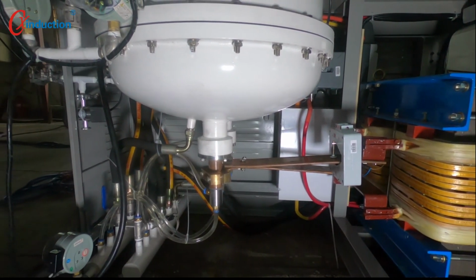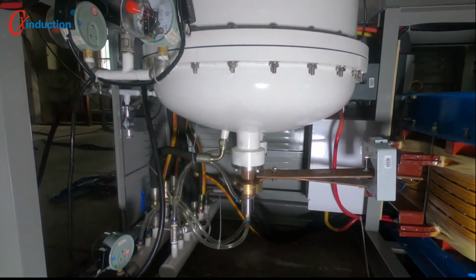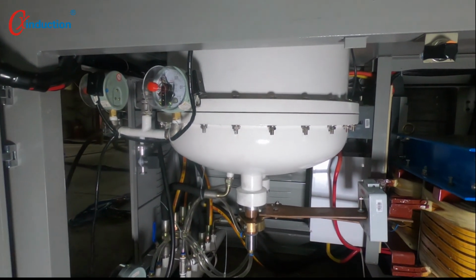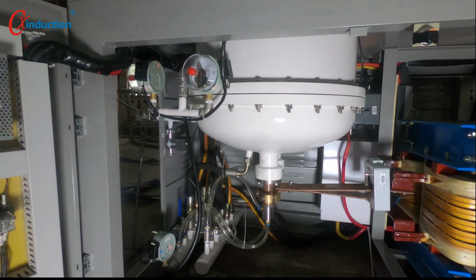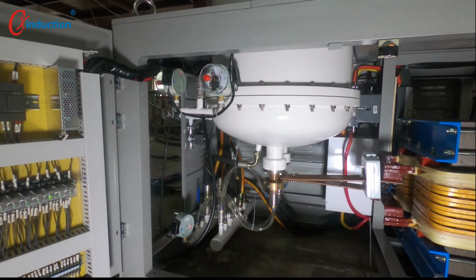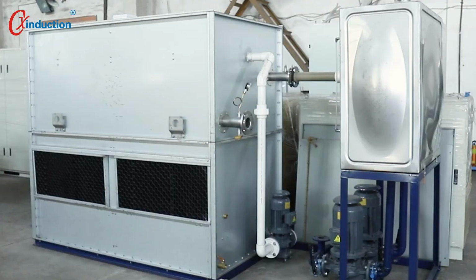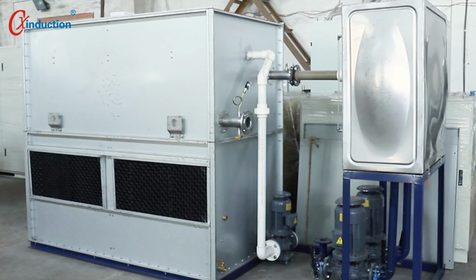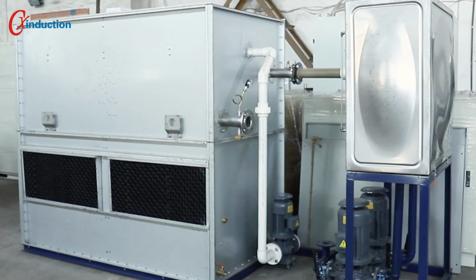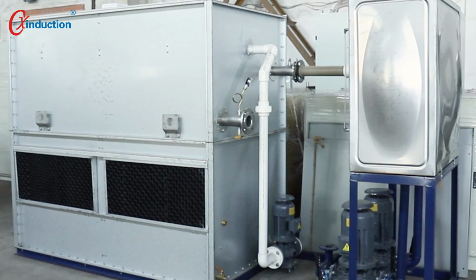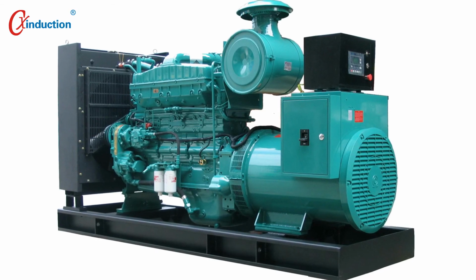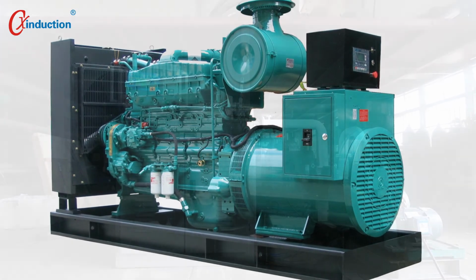The carbonization furnace works under high temperature for a long time. In order to maintain good operating condition, in addition to the configuration of a closed cooling tower to supply cooling water to the furnace, an emergency water supply must also be provided. A generator can also be used to supply power to the cooling tower.